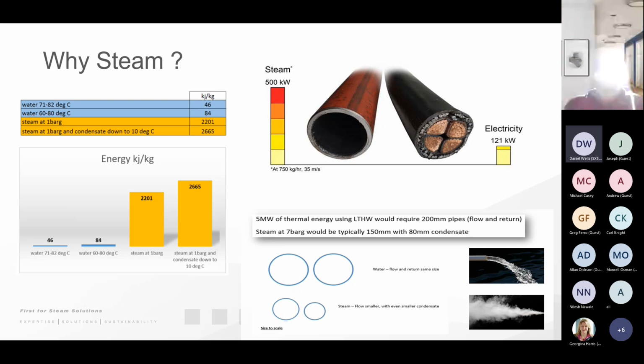So if we look at the image up towards the top right-hand side of the screen, that really reminds us that we can get far more energy down a steam pipe than we can down an electrical cable as an alternative. Down in the bottom right-hand side of the screen, you can see that because there's so much energy contained within a mass of steam, and because steam is, after all, a compressible gas, we can distribute that steam, we can move that energy hundreds, thousands of meters around site in a very small and cost-effective infrastructure. Something that we can't do with water, because it's not a compressible fluid and there's far less energy contained within it. But furthermore, we don't pump steam. Steam's a gas and it moves in accordance with the pressure drop around the site. So if we're generating steam at a very high pressure and using it at a much lower pressure around the network, that steam will move from the higher pressure to the lower pressure without the need for any circulating pumps.